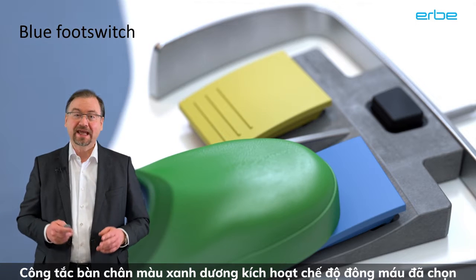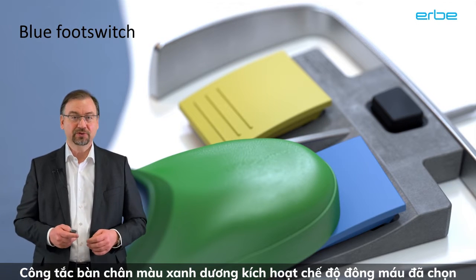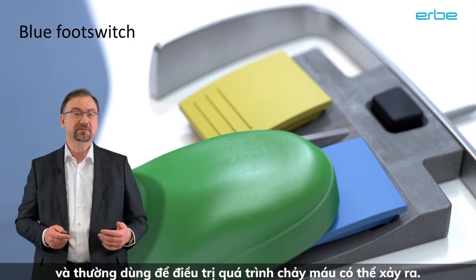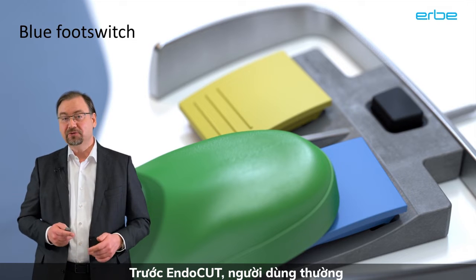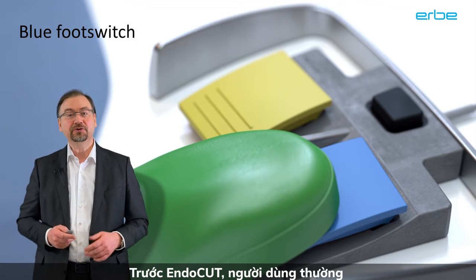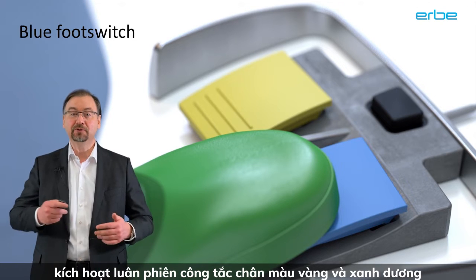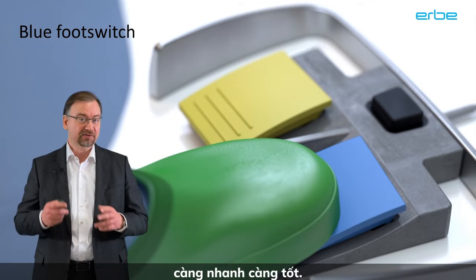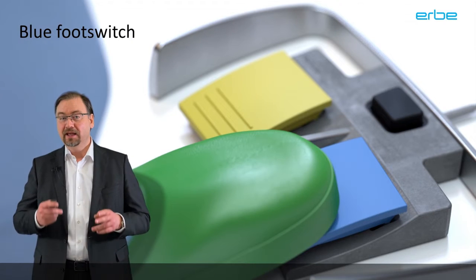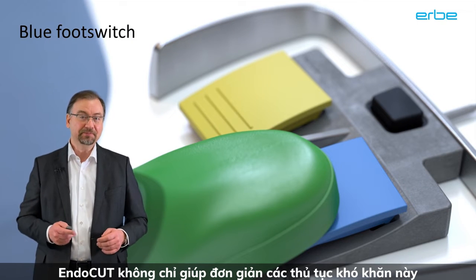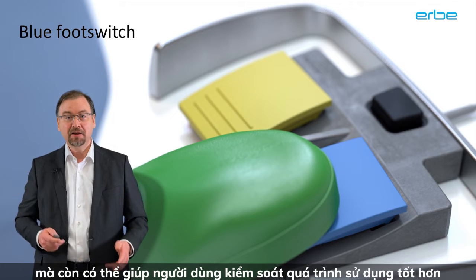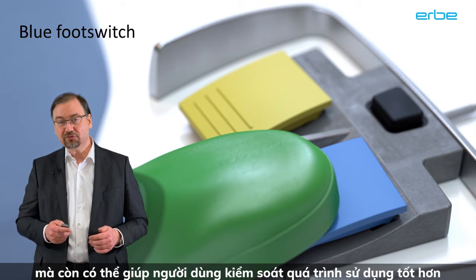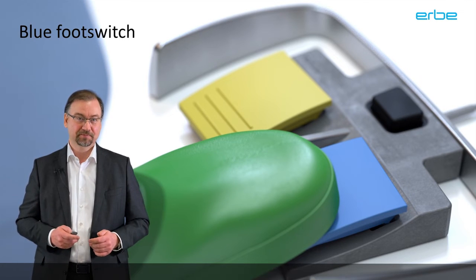The blue foot switch activates the selected coagulation mode and typically serves to treat possible bleeding. Prior to EndoCut, it was quite common for users to activate the yellow and blue foot switch alternatingly as quickly as possible. EndoCut not only helps to simplify this difficult procedure, but can also help to have a better control than by tapping the foot switch.